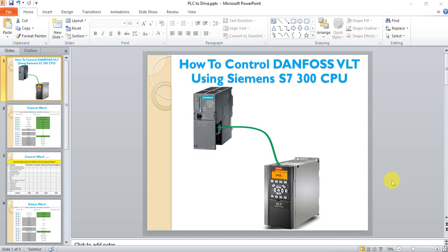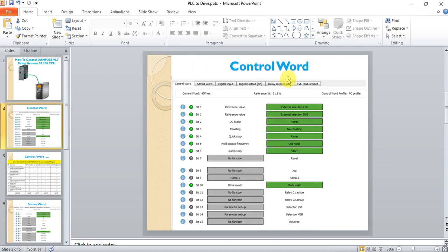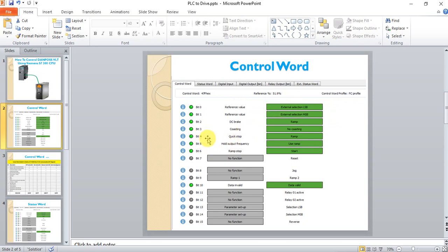Let's see some important notes. This is the layout of the ProfiNet profile. The first important parameter is the control word. It has 16 bits, or it is one word. For example, if bit 0 is 0 it means reference value; if it is 1 it means external selection. Likewise, if bit 4 is 0 it means quick stop; if it is 1 it means ramp.